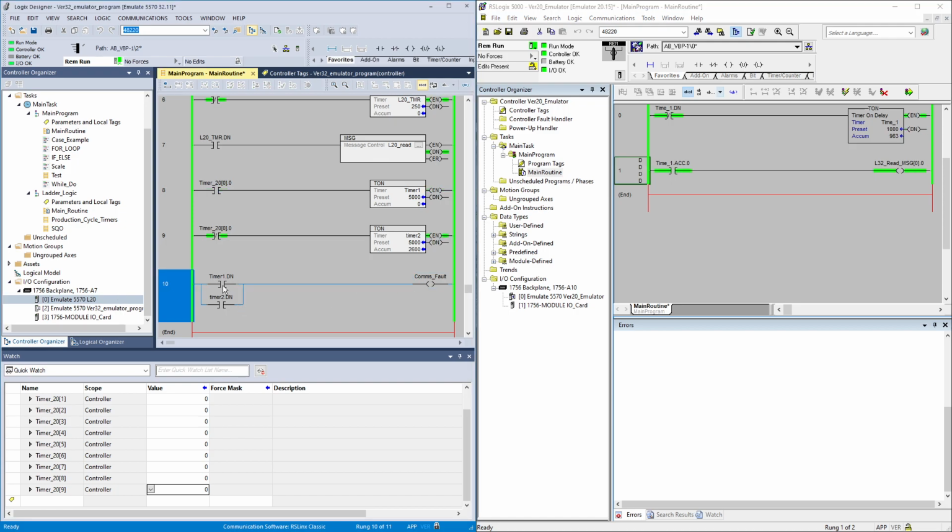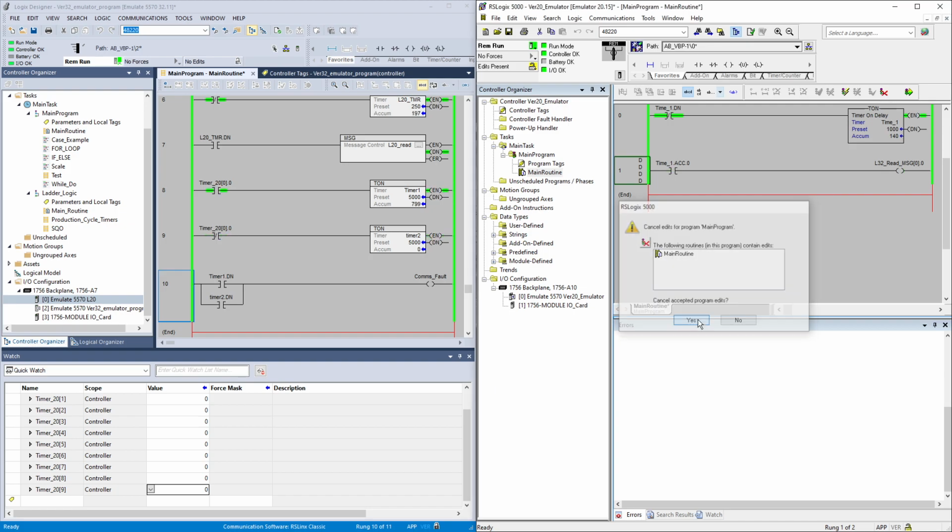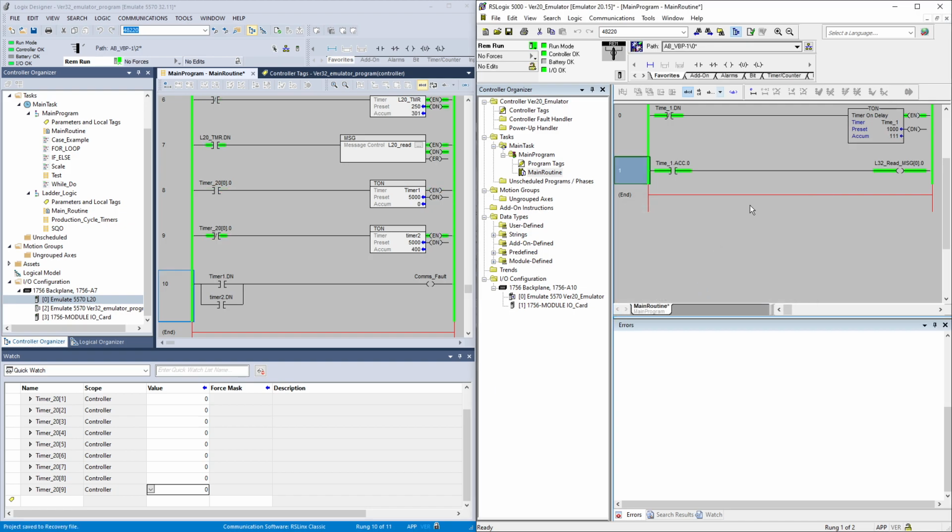There you go. So that's how you can create a watchdog timer between two PLCs to just make sure that the communication is good. Every single piece of data will be received within a time frame. There are different ways to create these watchdog timers, but this is one way to do that. And that's all about it.